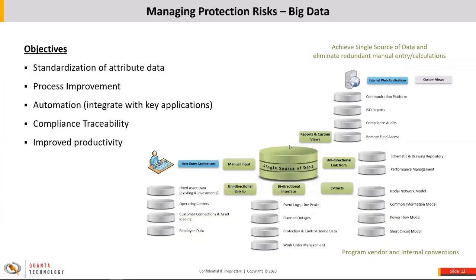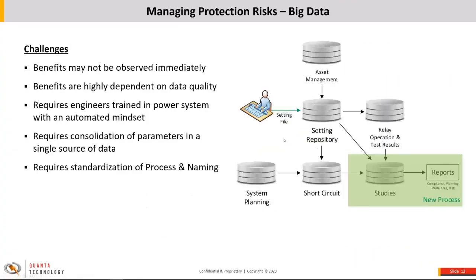You also need to find ways to program and generalize vendor and internal conventions so that even a non-protection engineer could understand the setting of a zone 2 distance element, regardless of which vendor you're using or whether you have a microprocessor relay or electromechanical. Essentially, we want to find an autonomous way to connect your main asset management repository into setting repositories such as AspenRDB and PowerBase, and have relay settings automatically pushed down to your short-circuit model in Aspen OneLiner.